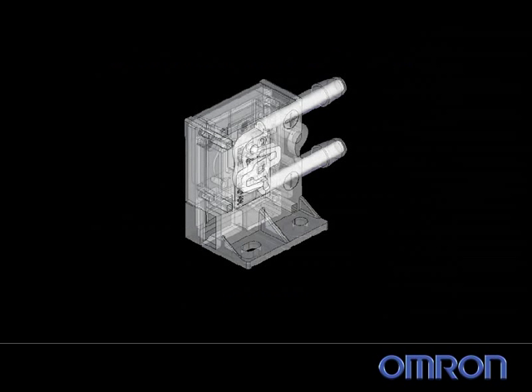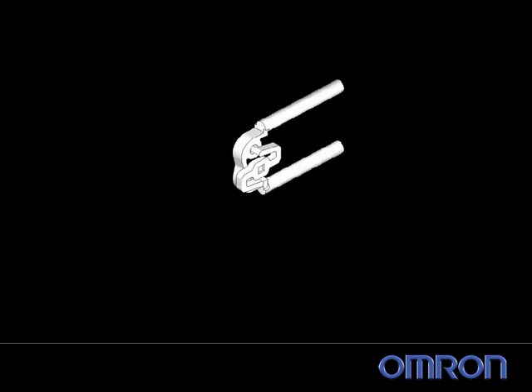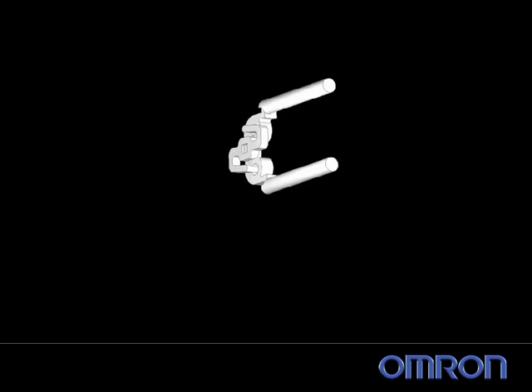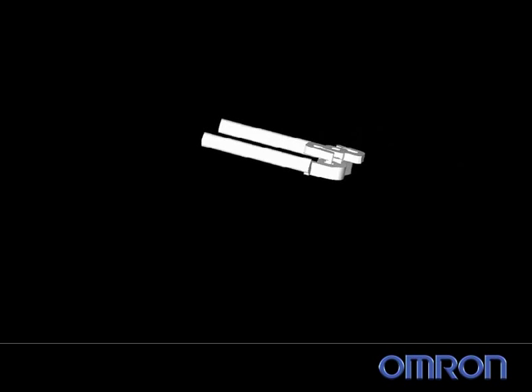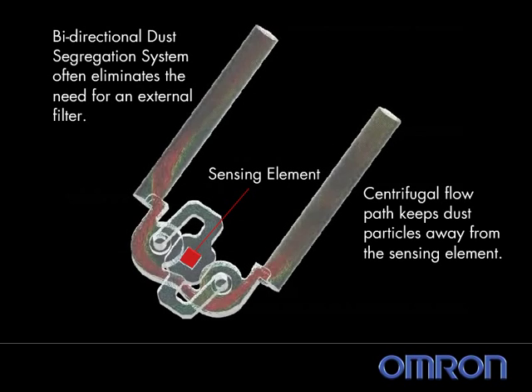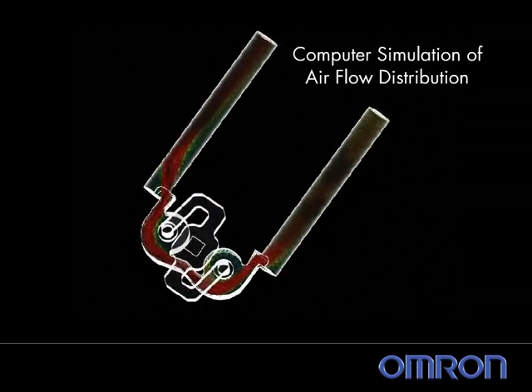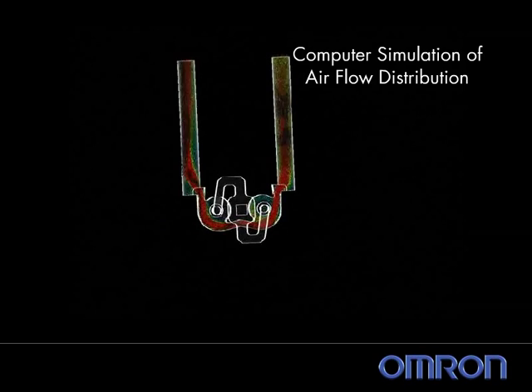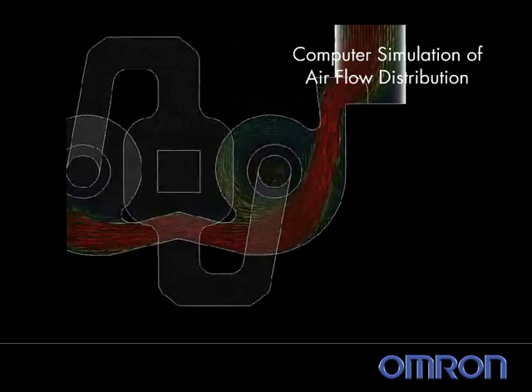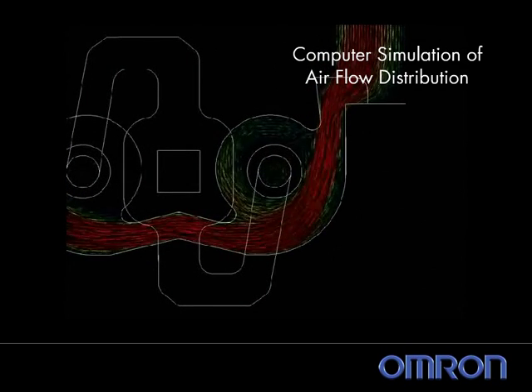The internal flow path of the D6FP is shown here. The two round chambers create a centrifugal force in which heavy dust particles are pulled to the outer flow path and clean air flows through the center path over the MEMS chip. This illustration of the air velocity pattern through the sensor chambers was created by a computational fluid dynamics (CFD) analysis of the flow path design.